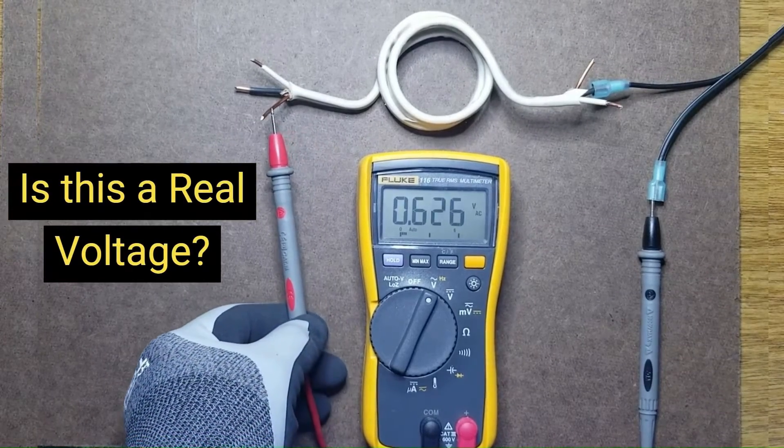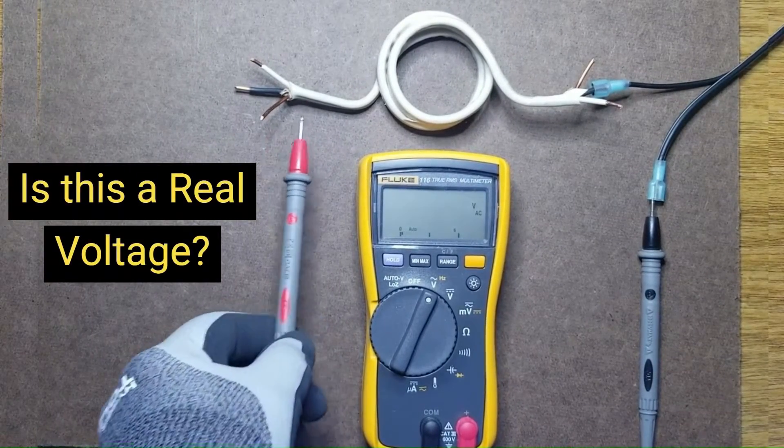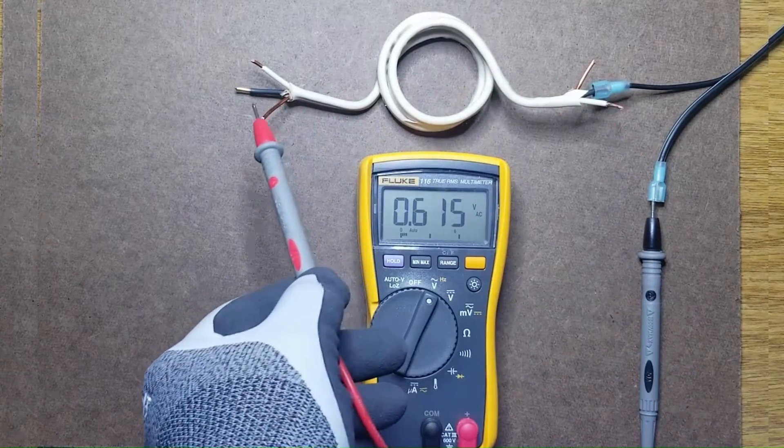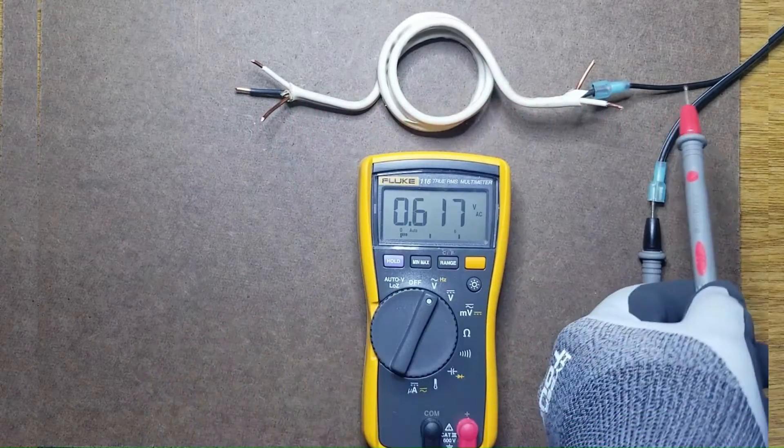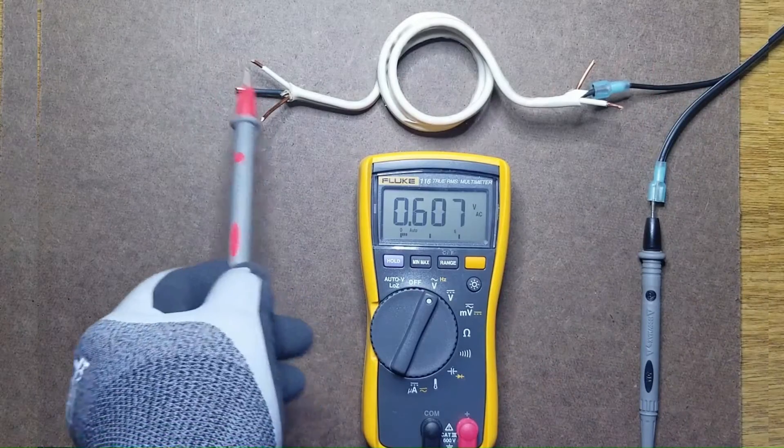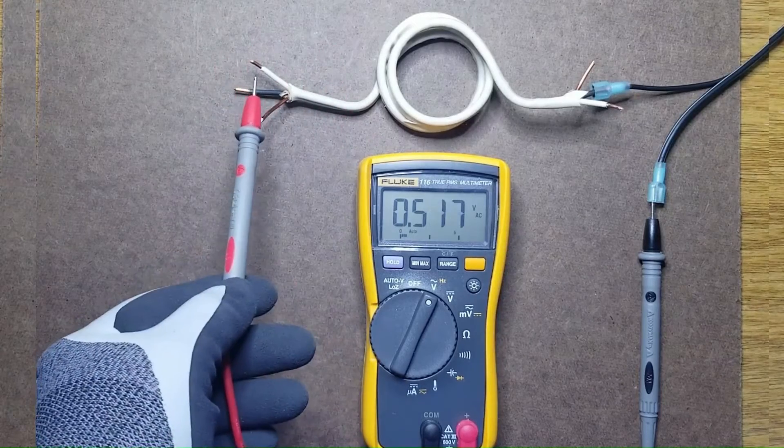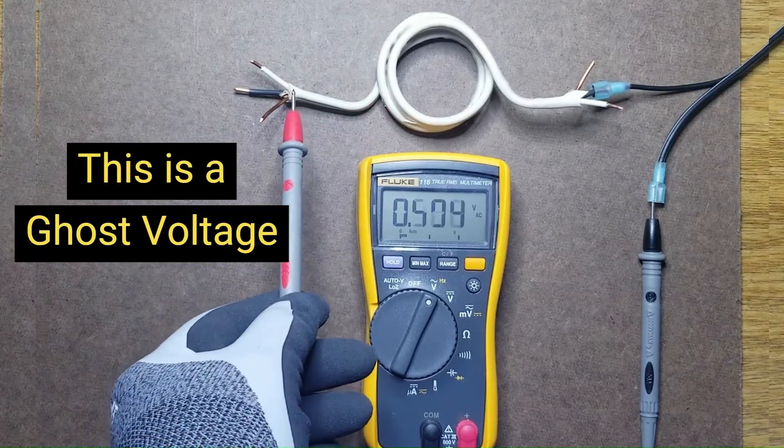Is this a real voltage? It is on a bare copper wire that isn't connected to anything. Although it's in close proximity to this black wire that has 120 volts on it, it isn't actually connected to it. This is a ghost voltage.